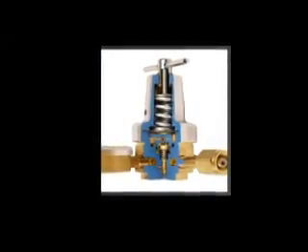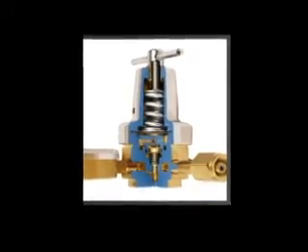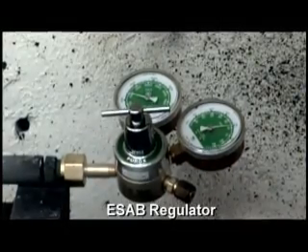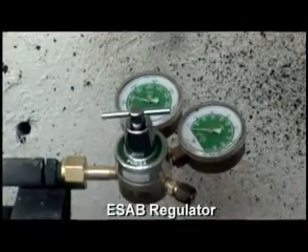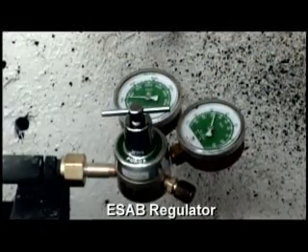Small bleeder holes in the baffle plate allow the diaphragm to function and respond to demand for greater or lesser amounts of gas supply. This baffle system prevents the fire from reaching the low-pressure chamber, where the potential for an explosion is the greatest. Using a relatively small quantity of seat material lowers burnout intensity should one occur.